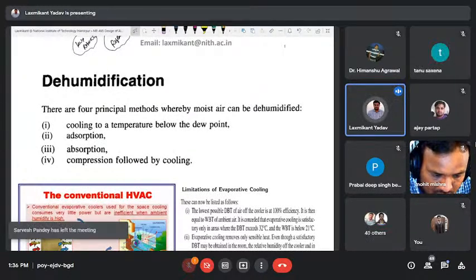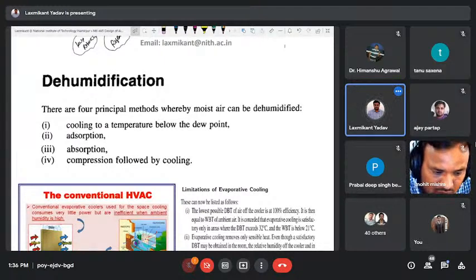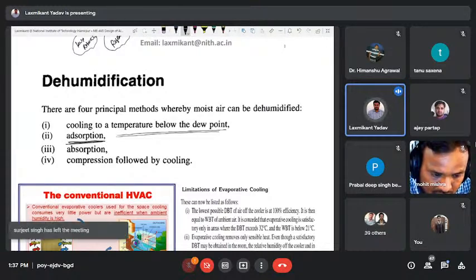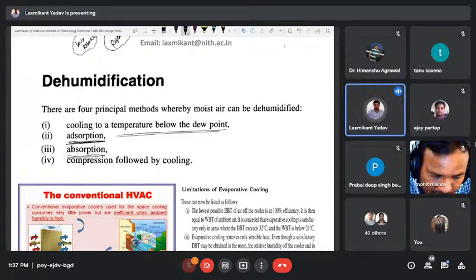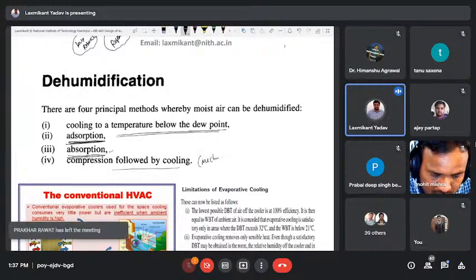So dehumidification, you already know. There are four principal methods whereby moist air can be dehumidified. As you can see in the slide, the first method is cooling to a temperature below the dew point, which we can call conventional dehumidification. The second is adsorption, when a solid desiccant is used for the removal of moisture. Absorption is when a liquid desiccant is used for the removal of moisture. And compression followed by cooling is also called mechanical dehumidification. Here we compress the air above the dew point temperature, then we cool it.